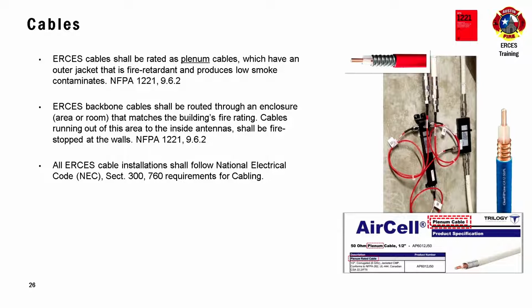When you do the backbone cables, they have to be routed through an enclosure, area, or room. It's kind of confusing when you use the enclosure part, but essentially it has to match the building's fire rating. So if you have a high rise, for instance, I think I mentioned this previously, you would need to have that backbone running and the equipment installed in a 2-hour rated stacked room. There are some other options we can look at for the cabling if that's not possible. All those cable installations have to follow the National Electrical Code.